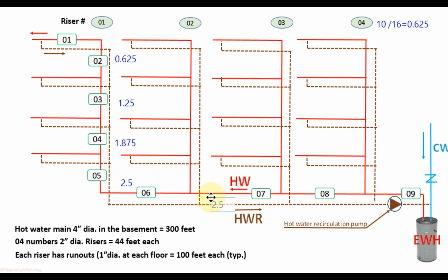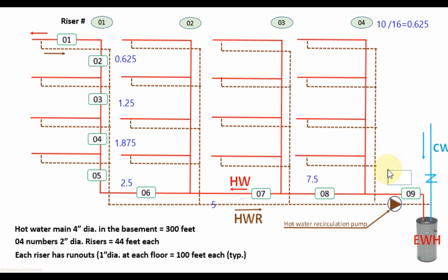For pipe segment 7, there are 2 risers connected before it, so 2.5 + 2.5 = 5 GPM. For pipe segment 8, there are 3 risers connected before it, so 2.5 × 3 = 7.5 GPM. For pipe segment 9, with 4 risers connected before it, 2.5 × 4 = 10 GPM. So the GPM at the end before the pump is 10 GPM.